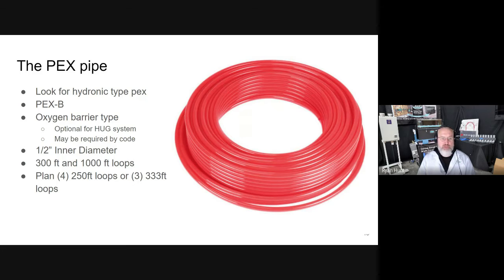Those typically come in 300-foot and 1,000-foot rolls. So when you're planning that, you plan 4 250-foot loops to use that material effectively, or 3 333-foot loops. I know the guideline I mentioned was 300-foot, but it's not critical. If you get just over 300, it's not going to stop working.